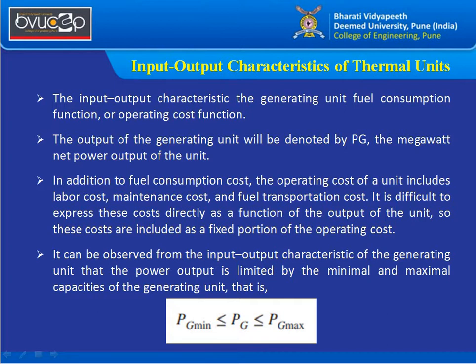The input is measured in units of fuel consumption, and the incremental cost depends on the type of boiler and turbine used. The output of the generating unit is Pg, the net megawatt power output. Along with fuel consumption cost, we consider operating cost, which includes labor cost, maintenance cost, and fuel transportation cost. These are treated as fixed proportions; only the incremental cost for power generation is variable.